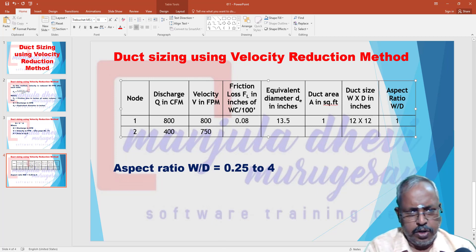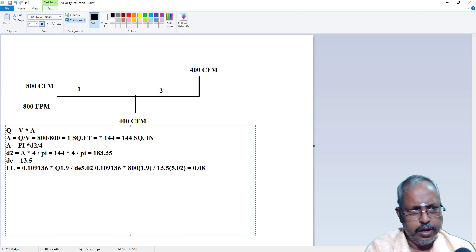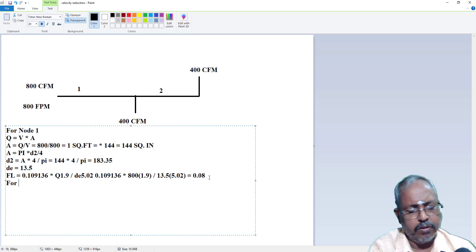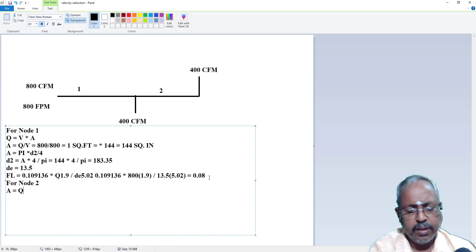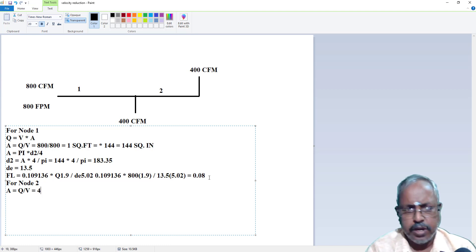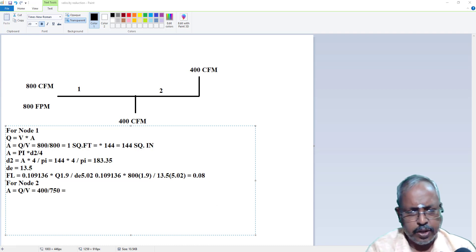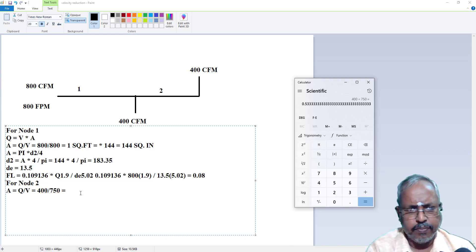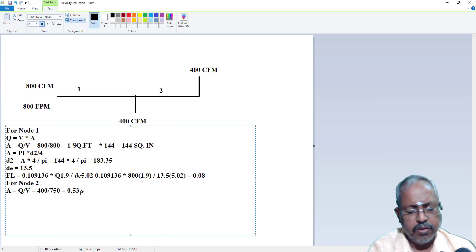Now for node 2: A = Q / V. Q equals 400 CFM, velocity equals 750 FPM. So 400 divided by 750 equals 0.53 square feet. Converting: 0.53 × 144 = 76 square inches.